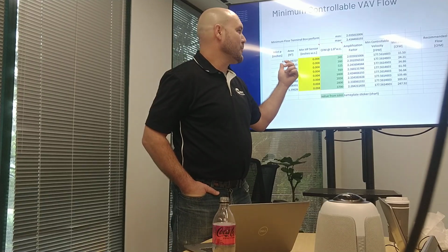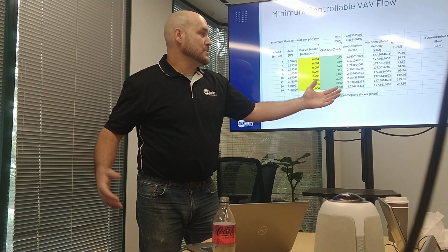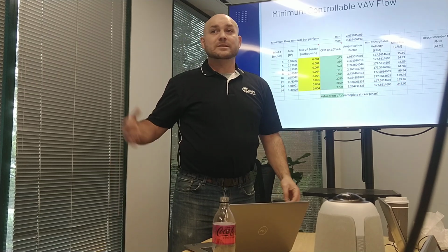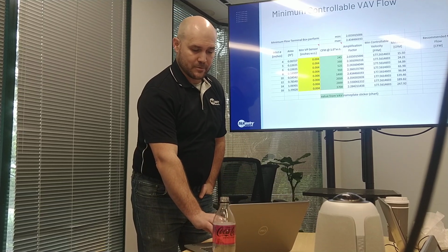And then based on the box size, 4 inches converted to the cross-sectional area would give 15.5 CFM. And then in terms of the values we want to control to, you want to round up from there just to be a little safe. So we said 20, and these, again, how much safety factor you want to put in here. For 96.84, you could maybe say 100 or 105. You said 110 in this instance. So yeah, maybe you could say 250 for this bottom one. I said 275, which compared to the actual controllable flow for the box, it's doing like a couple thousand CFM. So getting down to whether it's 250 or 275, it's a significant reduction from what probably the minimum airflow for that box is currently set to.